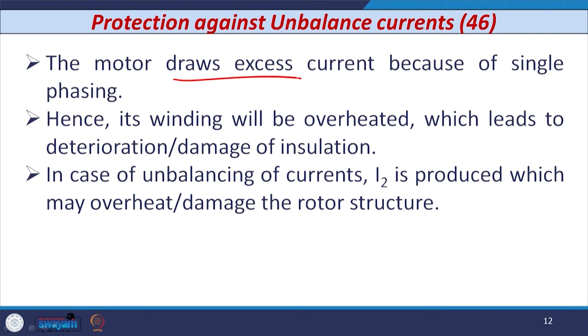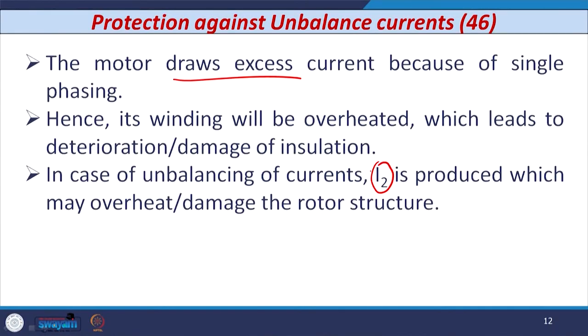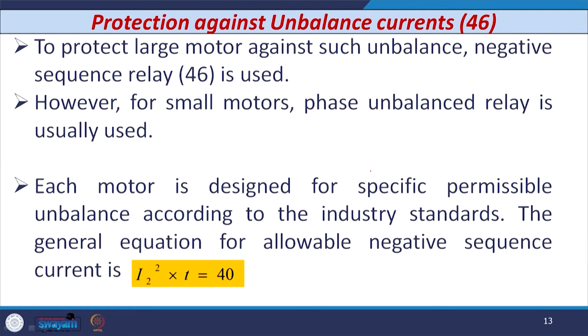The motor in this situation draws very high current because of single phasing, hence its winding will be overheated, which leads to deterioration of the insulation or sometimes damage of the insulation. In case of unbalanced current, negative sequence current I2 is produced which may overheat or damage the rotor structure. The heat produced because of the negative sequence current is 6 times the heat produced when positive sequence current flows.